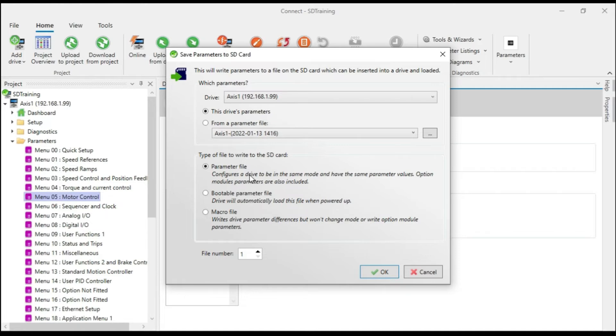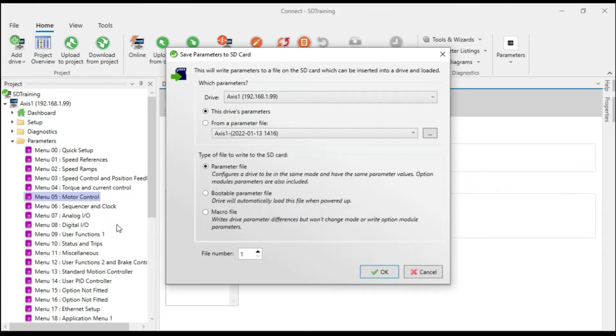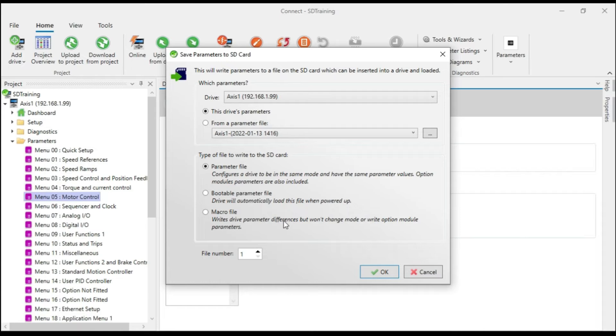And then down here, it's asking what type of file to write to the SD card. A parameter file gets everything, including any of the parameters for any option modules that are installed onto the drive. A macro file, however, is a little different. A macro file will copy all of the setup parameters here as a difference from default. So the only parameters that it's going to write are those that have been changed from the default value.